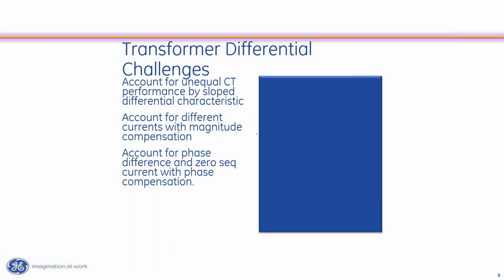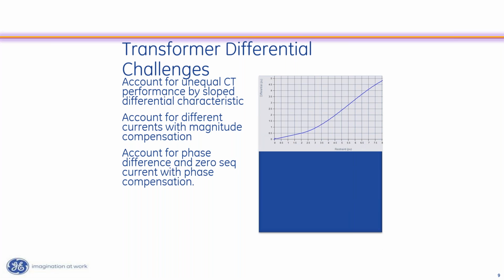Now the way that we take care of that in most differential schemes is we use something called a slope differential characteristic. And that's what I show here. On this slope differential characteristic, along this axis is restraint current, and along this axis is differential current. This blue line that I show there is the operate characteristic. If I'm above this blue line up in here, I'm in the operate region. If I'm below the blue line, I'm in the non-operate or the restraint region.